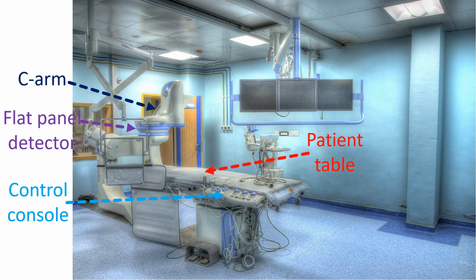X-ray equipment is mounted on a C-arm which can rotate in two planes to allow different angulated views. In the image, the flat panel detector situated above the patient table is shown, while the X-ray source below the patient table is hidden by the lead shield. Both these move together when the technician operates the C-arm from the control console. Patient table can also be moved to get the region of interest while imaging in the center of the image. This movement is known as panning, and can be done either by the operator or technician. Table can also be locked to avoid unexpected movements while doing procedures like skin puncture.